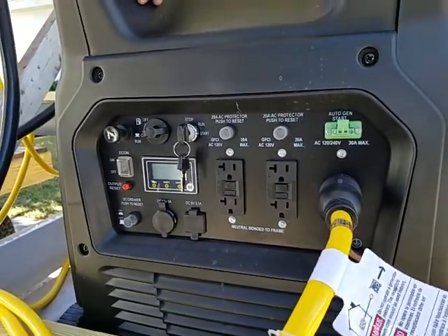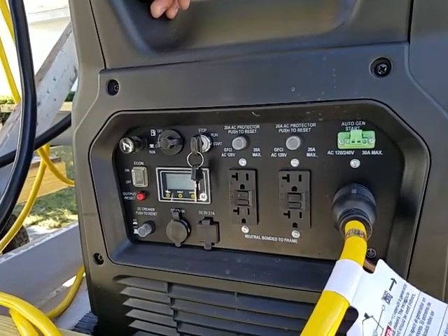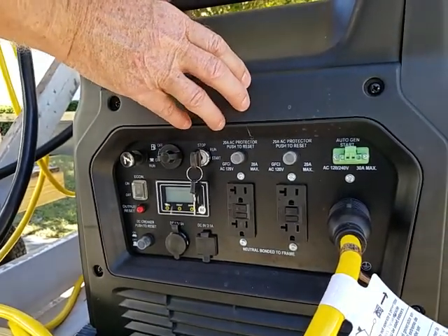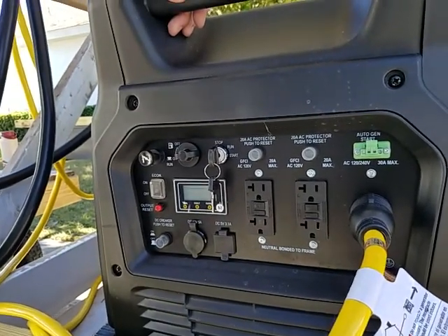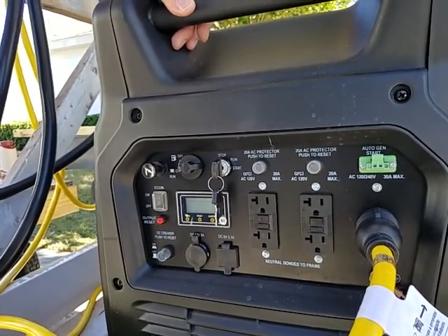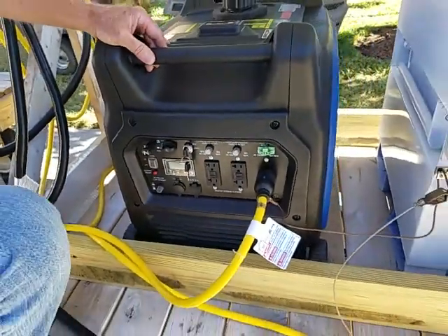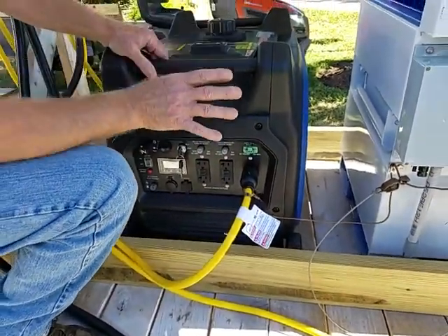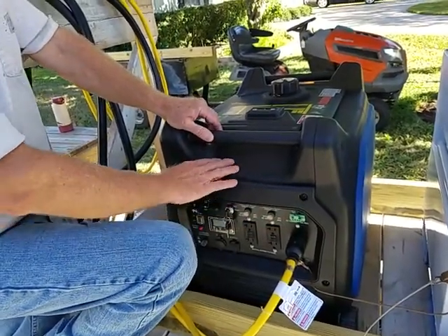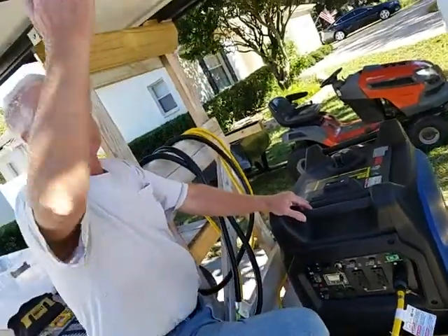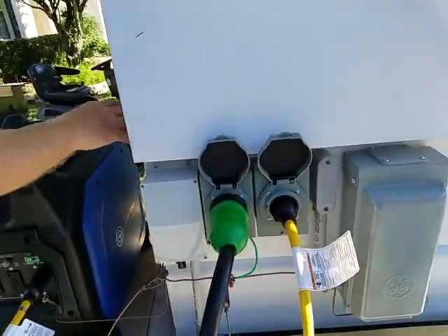And so with some parameters, not really programming because we're not writing code, we're going to go into menus, going to enter parameters, which will allow us to call on this generator to start when we reach a certain charge state for the batteries. Not a voltage state, but a charge state. You'll learn that it's very difficult to determine from voltage the state of charge for an LFP battery. But based on the state of charge for the batteries, we may call on the generator. We may never call on the generator. It's possible that we have enough energy from solar. It's possible that we have a grid connection and we draw our power from the grid.